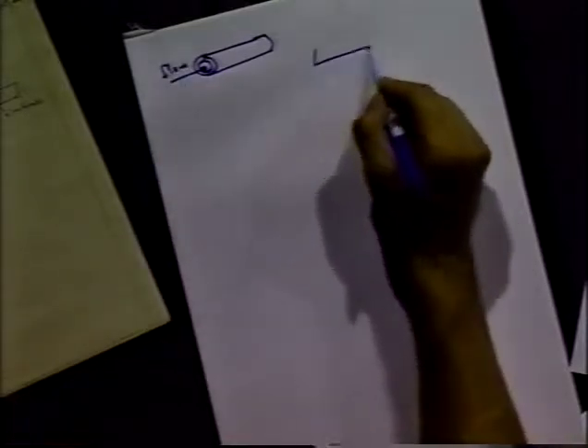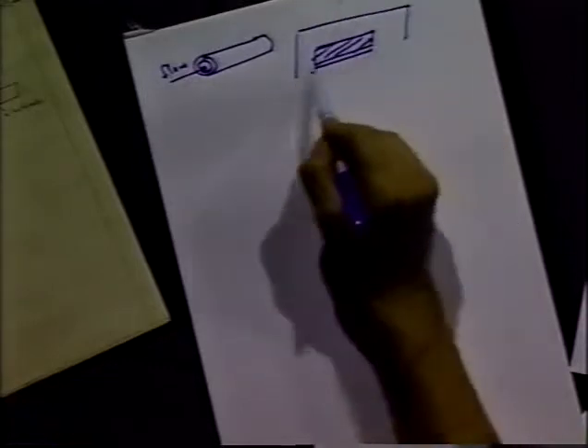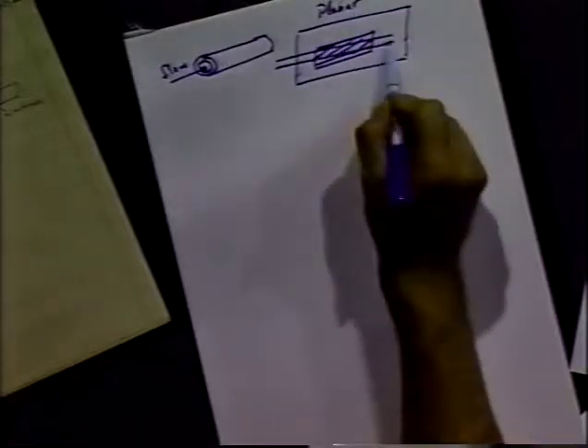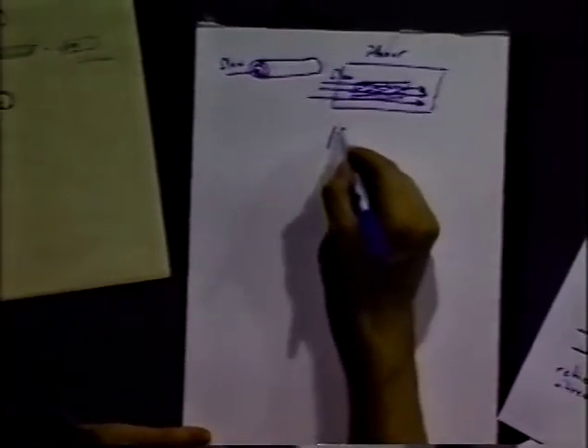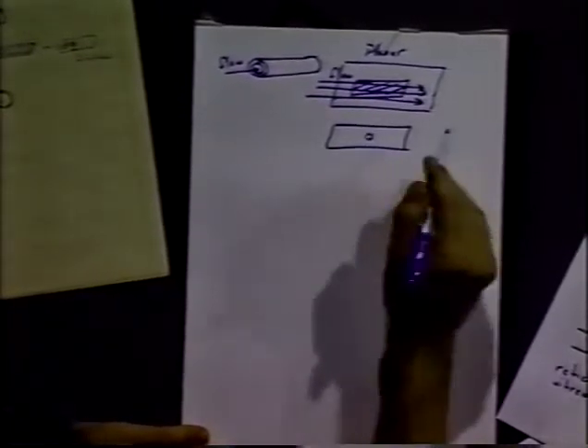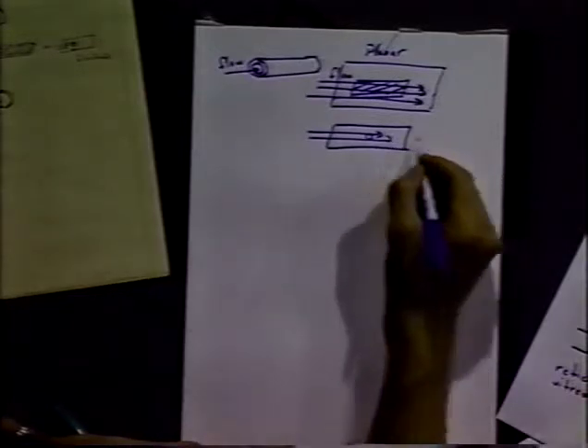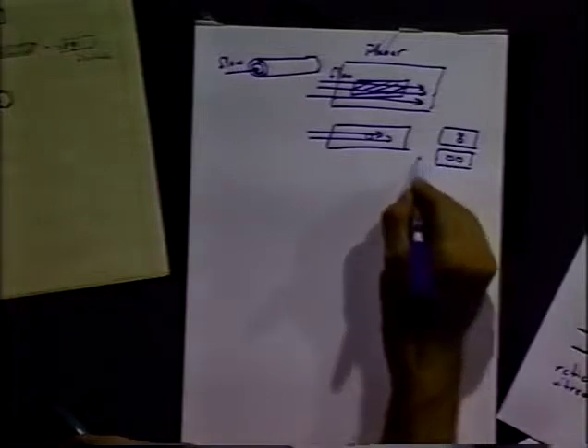Planar electrodes. You can have the electrode acting as a plane and the whole electrode can be a plane or it can be embedded in some other material so that you have an electrode in there. The important thing with these planar electrodes is that you can have flow parallel to the surface. In other words, the flow is flowing across the plane of the electrode in that particular way. That's not used like this so much, but you'll see a lot of times detectors, especially detection systems, having a disk in there and that would be your electrode as it flows past. And sometimes it's a disk, a single disk, sometimes it's a pair of disks. Either a pair can be opposed like so, or they can be serially arranged so that the flow goes over both of them. And by adjusting the potentials for the different electrodes, you can get some different types of detection methods, which we won't talk about right now.